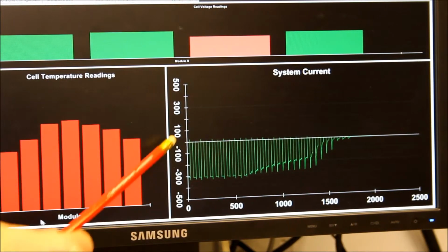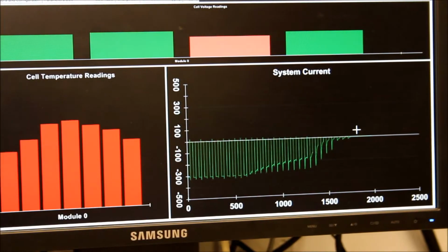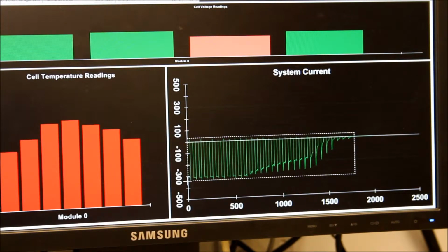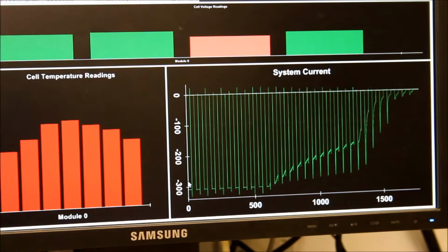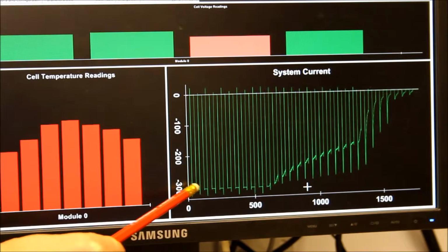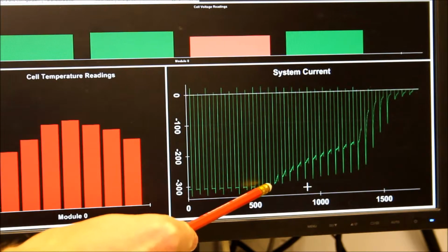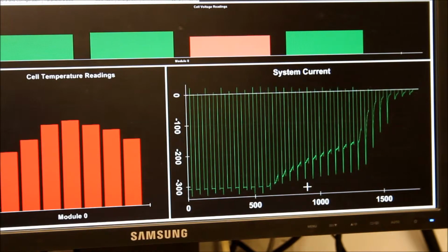Right, so could you zoom in a little bit here so we can see the current graph a little bit better? See what actually happened. That's good. Yeah. So the first 11 discharge bursts here, we've got virtually no, or we've got no current limitation, so the temperatures are well below 45 degrees centigrade, and then we are starting to limit the current because of temperature.